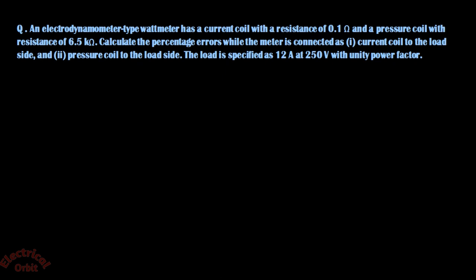Now let's see an application. An electrodynamometer-type wattmeter has a current coil resistance of 0.1 ohm and a pressure coil resistance of 6.5 kilohm. Calculate the percentage errors when the meter is connected with the current coil to the load side, and then with the pressure coil to the load side.